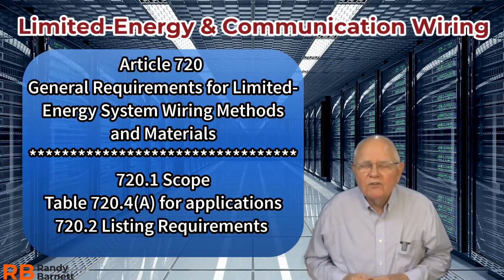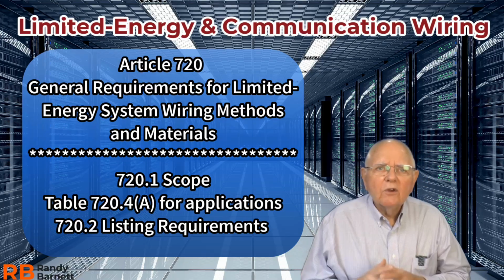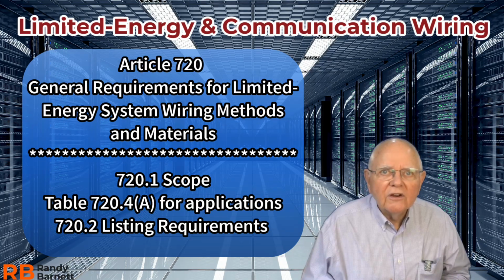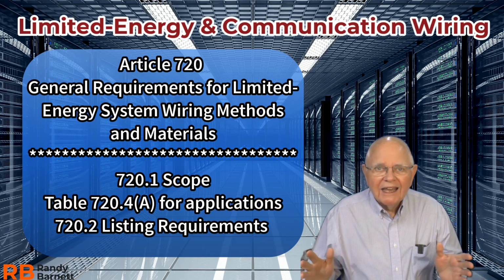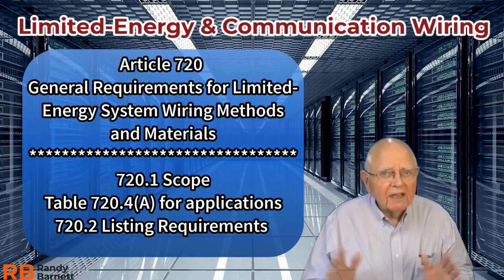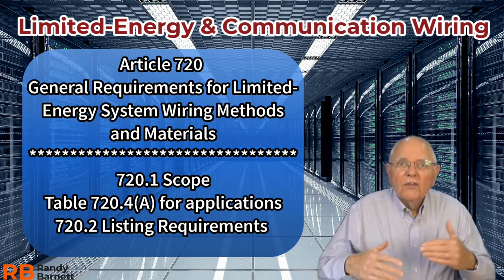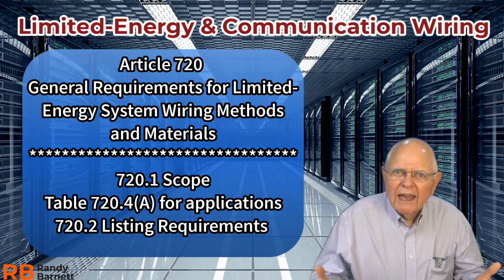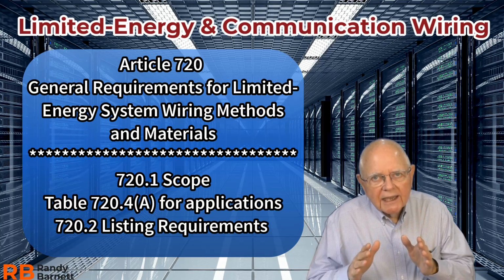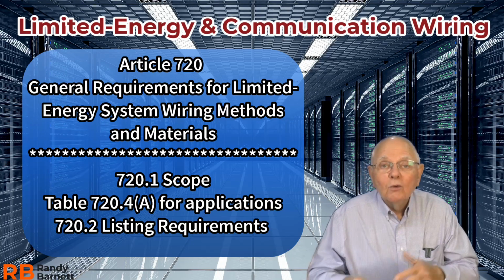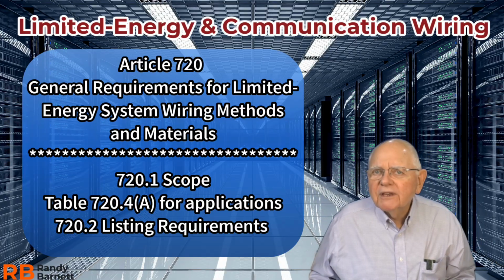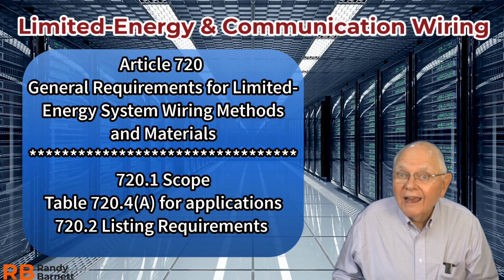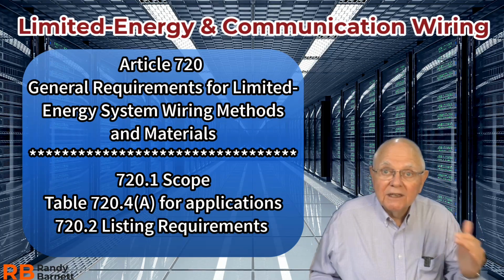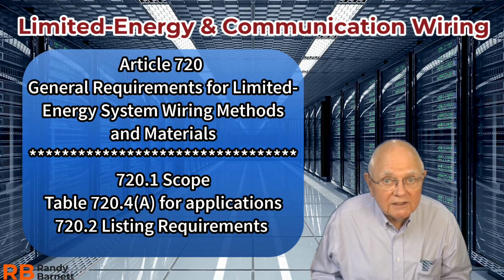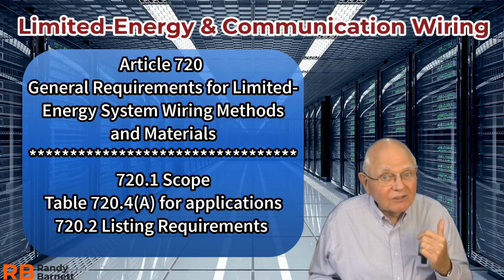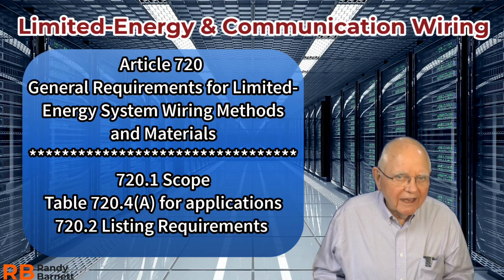So let's begin with Article 720. Article 720 is titled The General Requirements for Limited Energy System Wiring Methods and Materials. 720.1 is the scope, as it is throughout all articles in the code. And what is it talking about in Article 720? Well, things like signaling, fire alarm systems, broadband, so forth. In fact, there's a table, 720.4(A), which gives you a list of a dozen or so different applications. So that's a good table, 720.4(A), to take a look at to see where these limited energy systems apply. There is an informational note that says, hey, if you're talking about communication systems outside of a building, go take a look at Article 800.